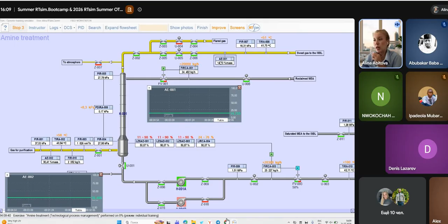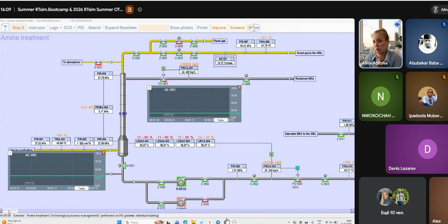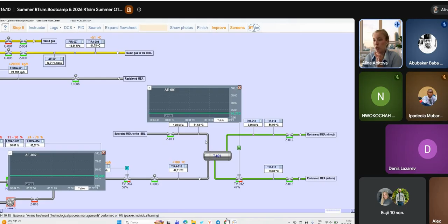And monoethanolamine, in turn, enriched with hydrogen sulfide, comes out from the bottom of the column, from here. And this is pumped. As you can see here, we have two pumps, and it goes to the heat exchanger here. And from the heat exchanger to the boundary of the installation. So, in fact, contaminated monoethanolamine can also be recleaned and again go to regenerate the incoming gas. Yeah, from here it's actually going like this.